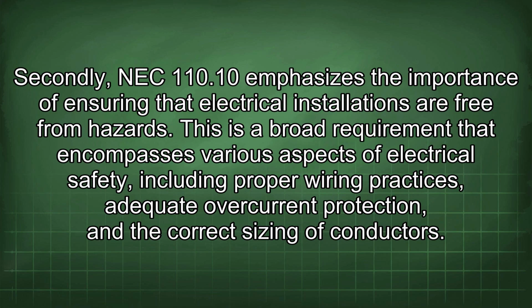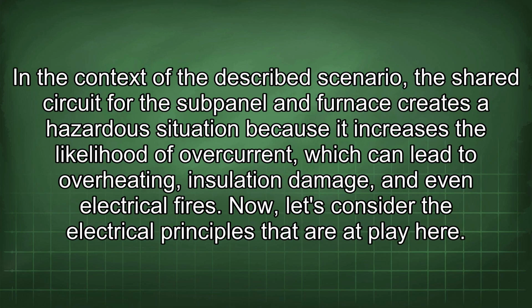Secondly, NEC 110.10 emphasizes the importance of ensuring that electrical installations are free from hazards. This is a broad requirement that encompasses various aspects of electrical safety, including proper wiring practices, adequate overcurrent protection, and the correct sizing of conductors. In the context of the described scenario, the shared circuit for the subpanel and furnace creates a hazardous situation because it increases the likelihood of overcurrent, which can lead to overheating, insulation damage, and even electrical fires.